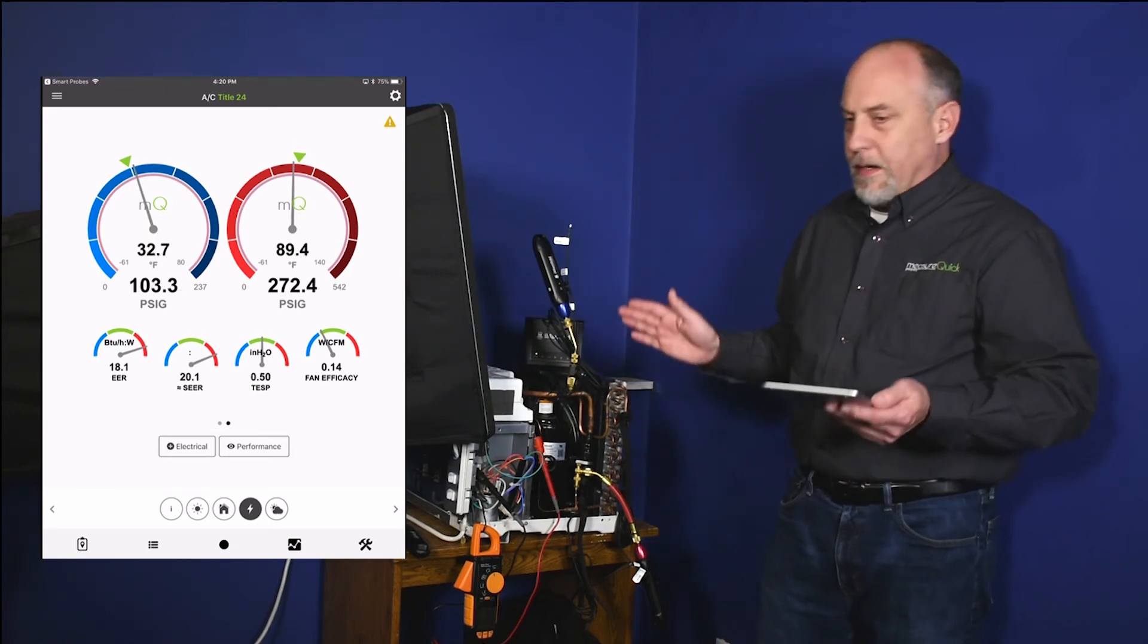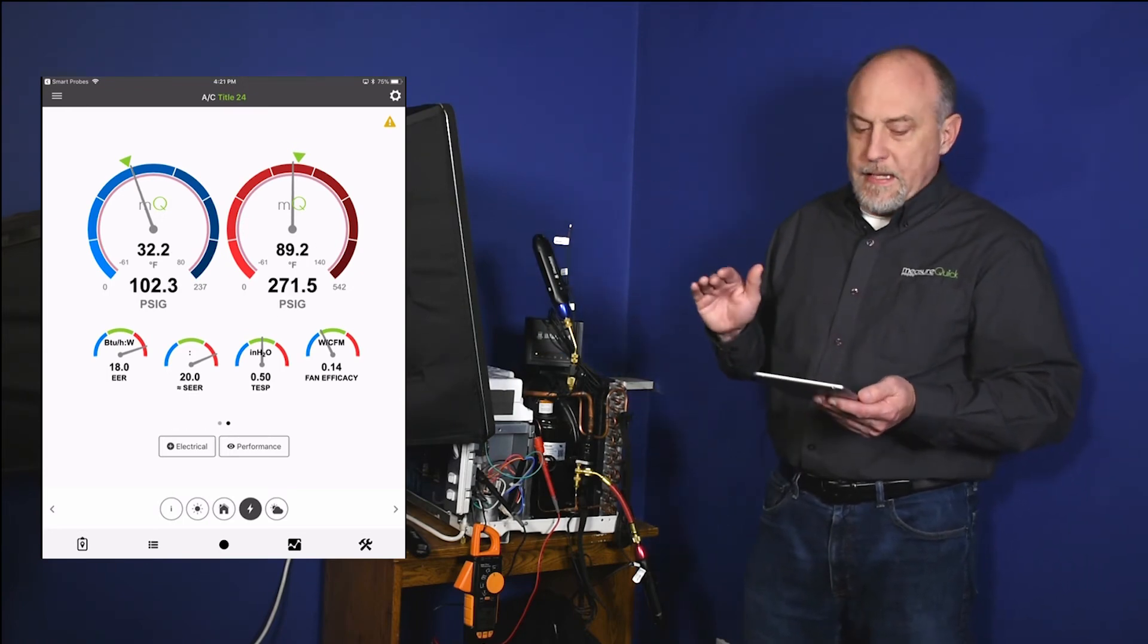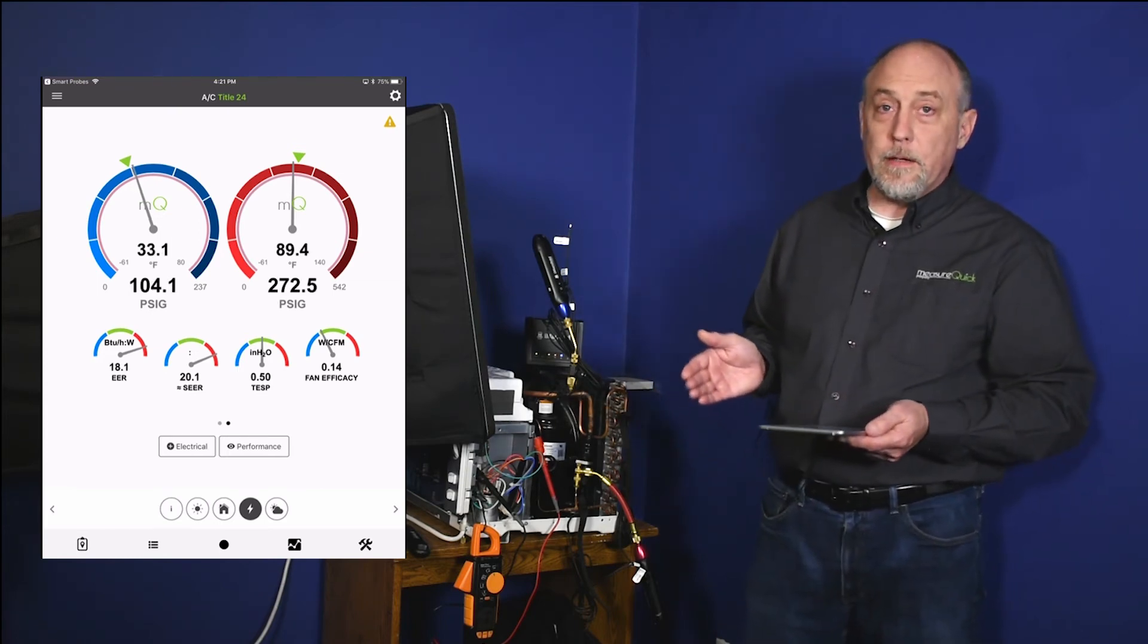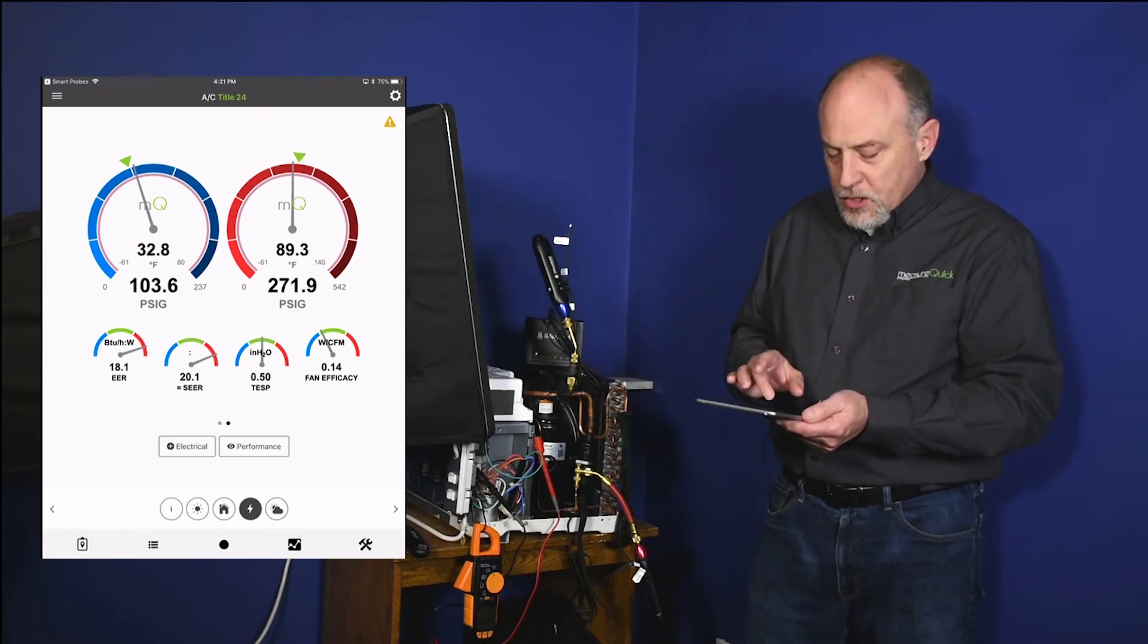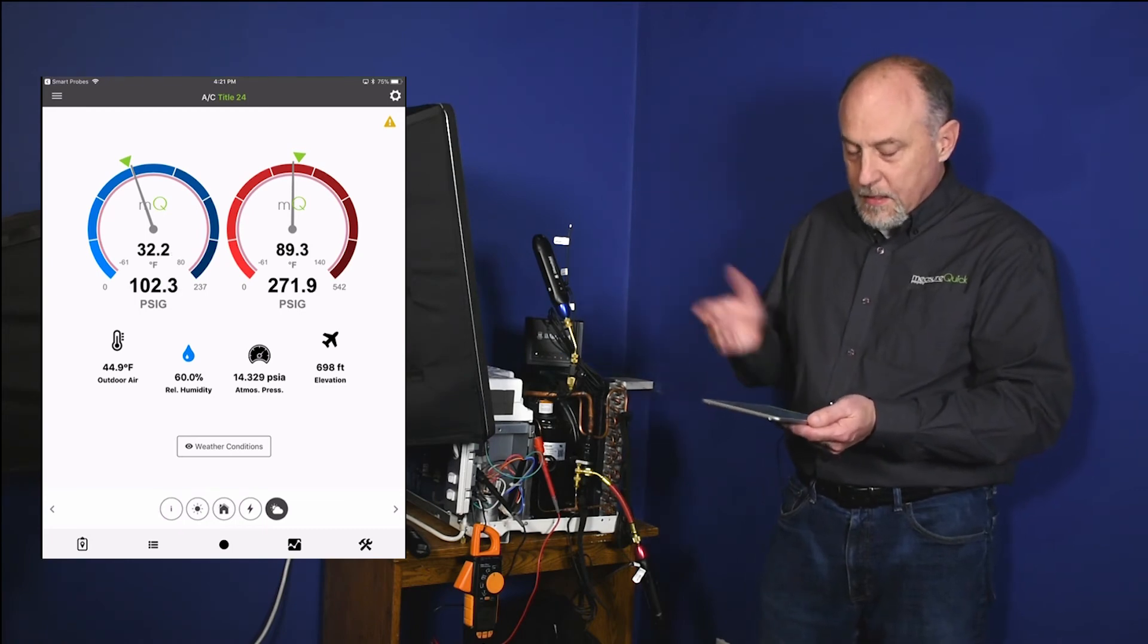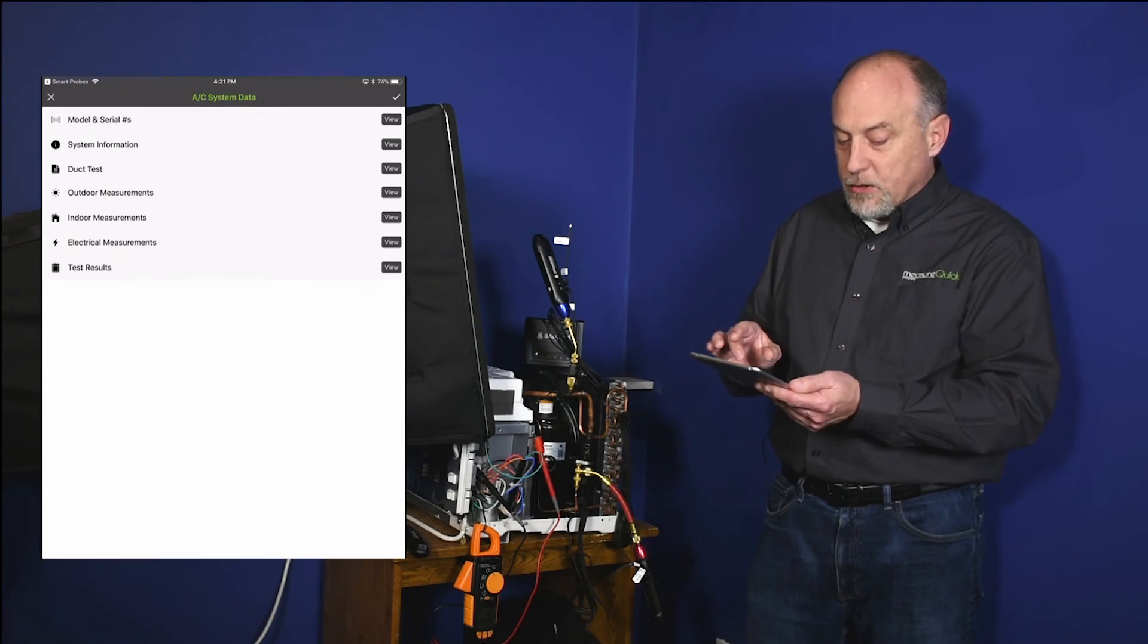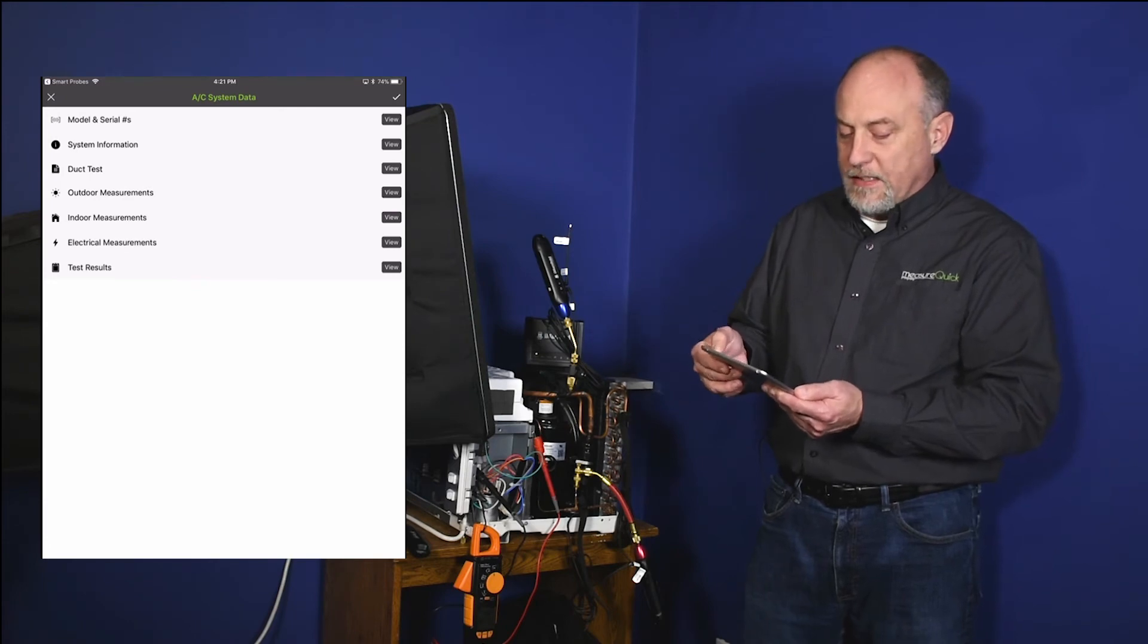So now hit the check mark button. All my readings are in. I got my EER, I got my SEER, I got my fan efficacy. All this stuff was looking good. Now again, we're in a house here, it's 30% probably relative humidity, it's dry. And so you can't rely on the EER readings and things like this. Again, this is sort of a convoluted little setup here, but it's designed to show you how the app works, not how a window air conditioner works here. So I can see I also captured my outdoor air data. It's pretty cold here today, 44 degrees. So now I want to go through, all that stuff is done. Go back to the home screen here and I can look at my test results. So this menu key allows us to look at all of the different things here.